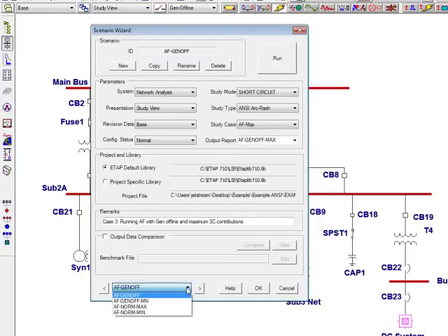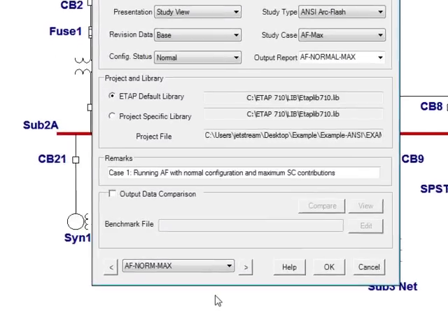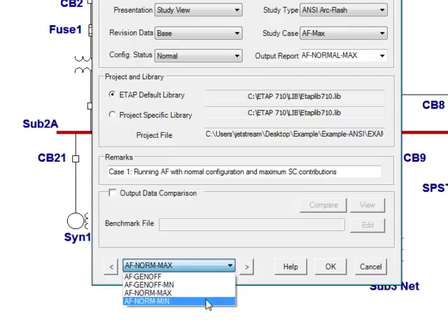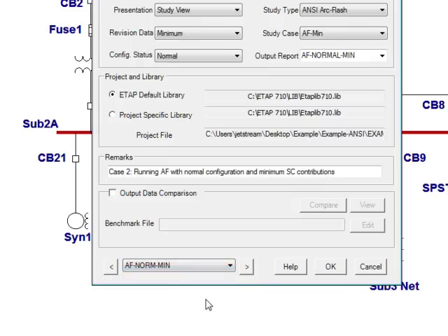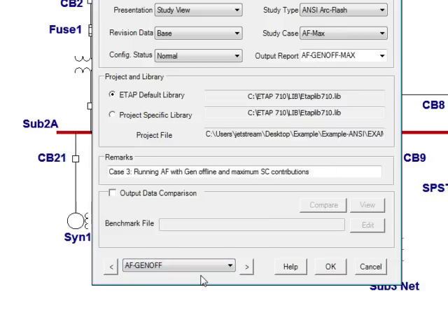Notice I have created four different cases. The first case, I'll be running ArcFlash with a normal configuration and showing maximum short-circuit contributions. The second case, I'll be running ArcFlash with a normal configuration and minimum short-circuit contributions. The third case, I'll be running ArcFlash with a generator offline and showing maximum short-circuit contributions. And last but not least, I'll be using case 4, running ArcFlash with a generator offline using minimum short-circuit contributions.